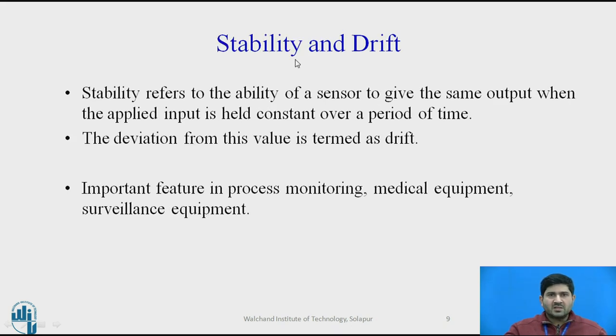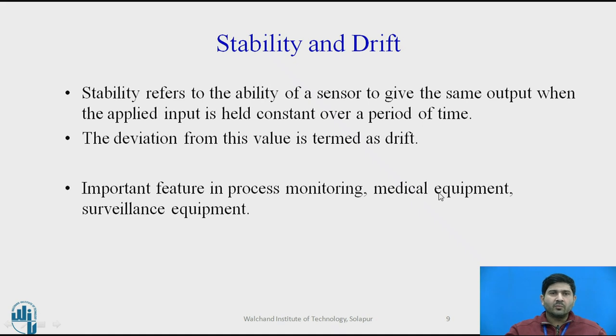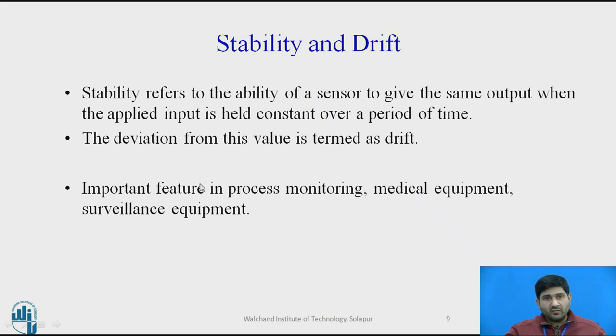Another important property is stability and drift. Stability refers to the ability of a sensor to give the same output when the applied input is held constant over a period of time, and a deviation from this value is termed as drift. For example, if a temperature sensor is measuring a temperature held constant in a salt bath over a period of time and shows a slight deviation, that is a lack of stability, and the deviation is termed drift. This is very critical in process monitoring, medical equipment, and surveillance equipment. Where prolonged measurement is expected, stability must be considered.